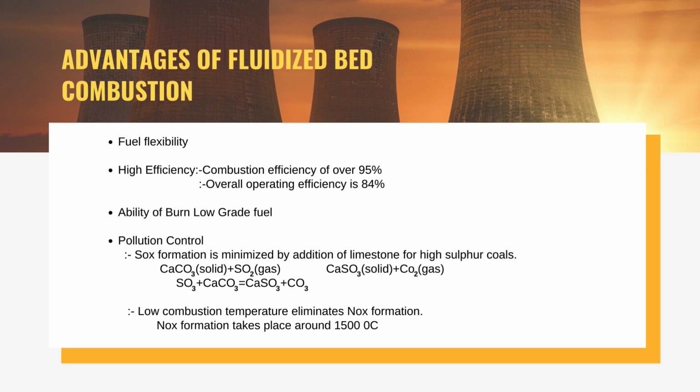CaCO3 solid plus SO2 gas gives CaSO3 solid plus CO2 gas. Low combustion temperature eliminates NOx formation, as NOx formation takes place around 1500 degrees Celsius.